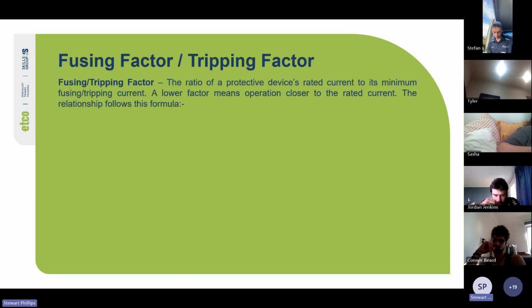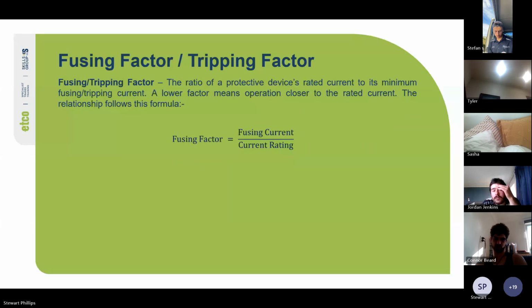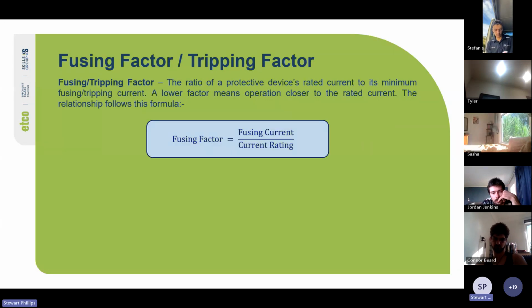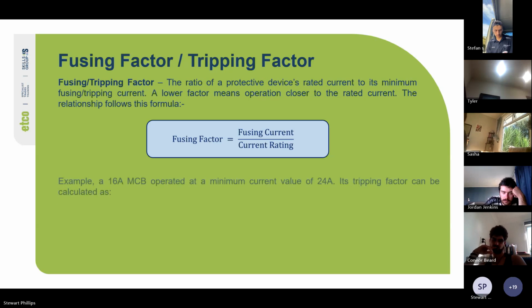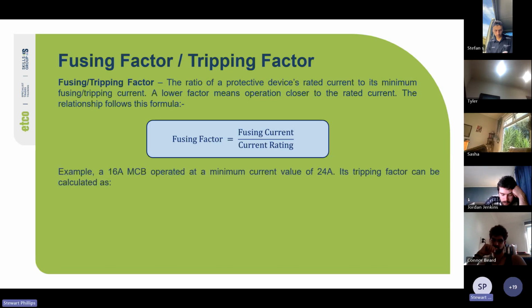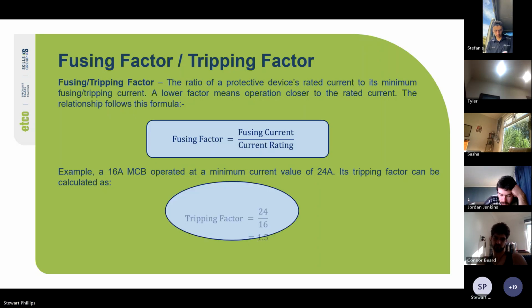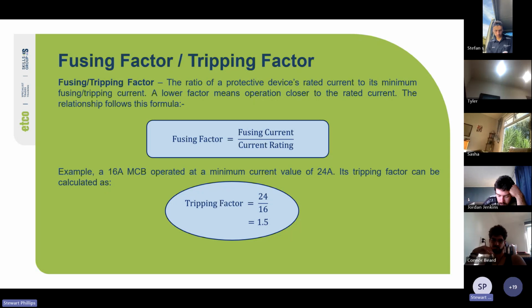Cool. So the fusing factor or the tripping factor is the ratio of a protective device's rated current to its minimum fusing/tripping current. A lower factor means operation closer to the rated current. The relationship follows this formula: fusing factor equals fusing current divided by current rating. So for a 16 amp MCB with a minimum tripping current of 24 amps, the tripping factor equals 24 divided by 16, which gives a tripping factor of 1.5. So the MCB operates at a minimum of 1.5 times its rated current.